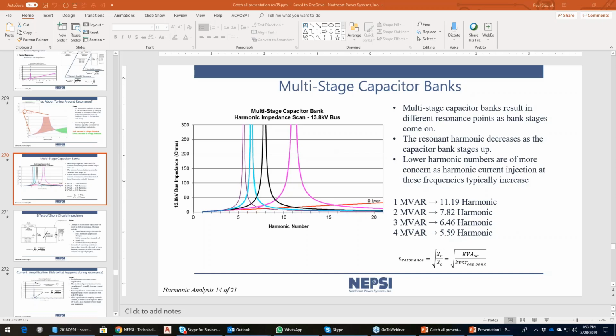So the first question that came in is, what's the main technical difference between using a harmonic filter versus a capacitor bank? What I put up here on the screen is just an impedance scan for a multi-stage capacitor bank. There are 4 stages here, and as these stages come on, you can see that there's a resonant point that exists for the stages. There's a 0 Mvar line here, the straight red line, which is just a straight impedance line. As we switch on 1 Mvar, 2, 3, and 4, you can see that we cross resonant points at the 11.19. We drop down to 7.82, 6.46, and 5.59.